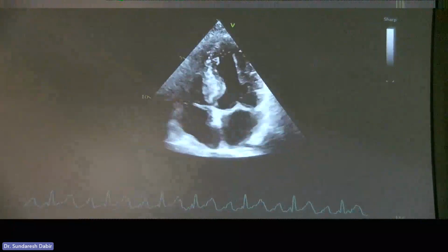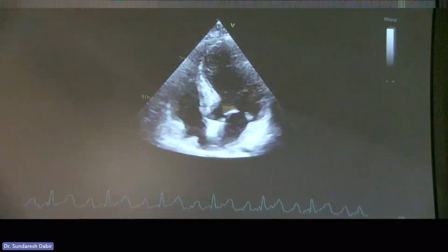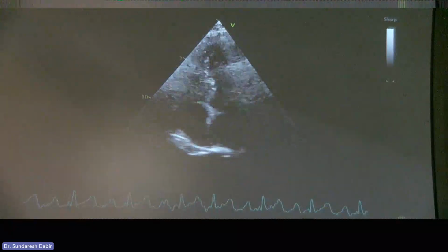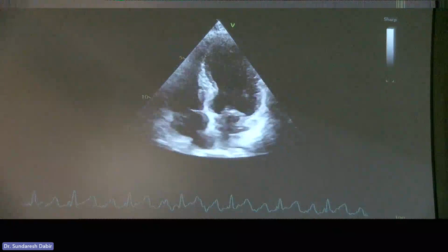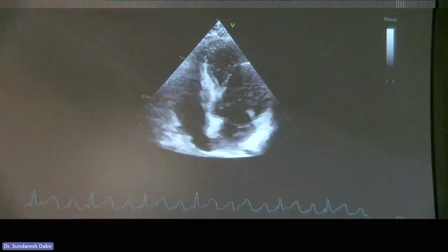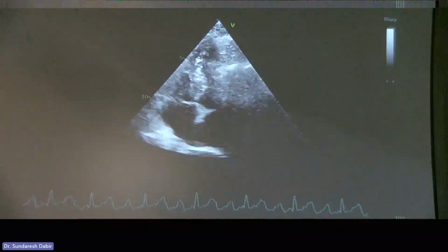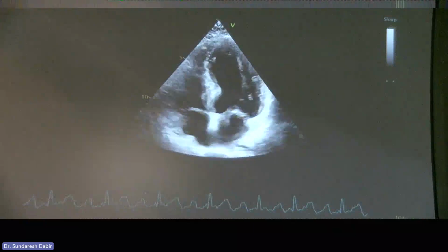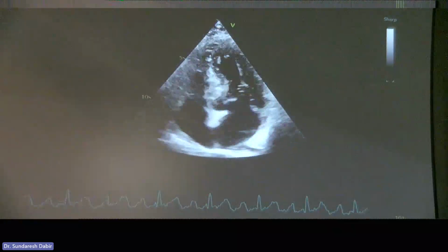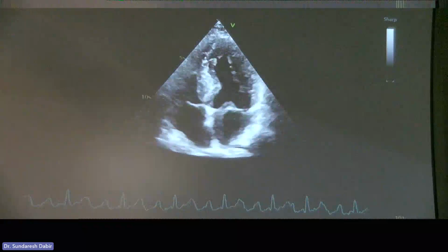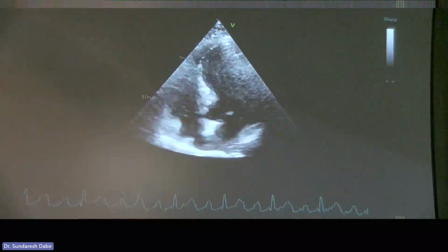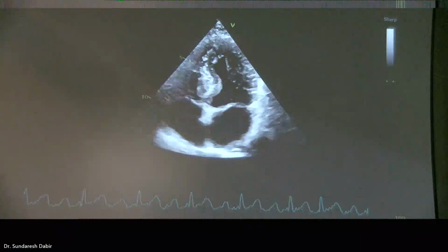Now, this is a transthoracic probe. The number is not shown on the screen, but this is about 1.4 and 2.8 megahertz. Most adult probes are between 2 to 5 megahertz. Pediatric probes are between 5 to 8 megahertz. So I can adjust my transducer frequency simply by changing the frequency on my probe. When would I do that, do you think?